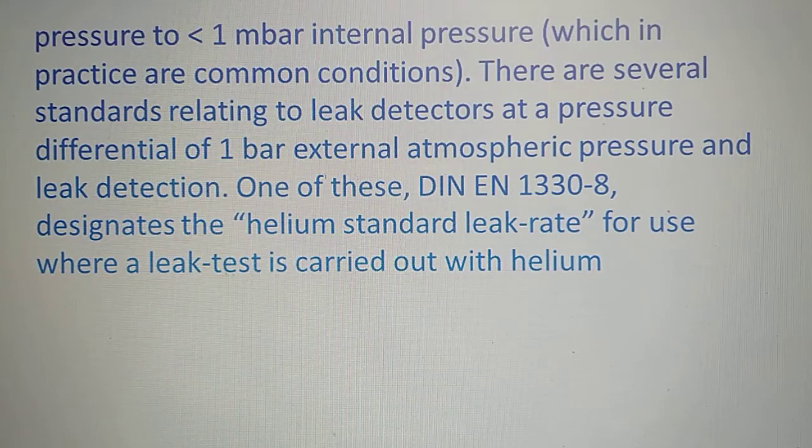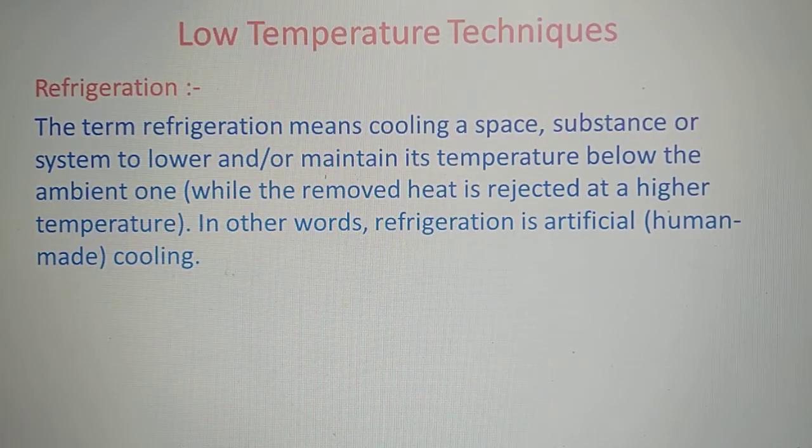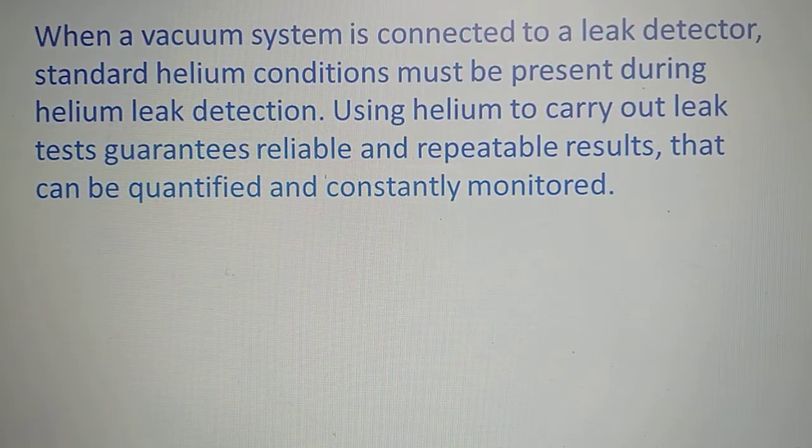One of these, DIN EN 1330-8, designated the helium standard leak rate for use where a leak test is carried out with helium, right? When a vacuum system is connected to a leak detector, standard helium conditions must be present during helium leak detection. Using helium to carry out the leak test guarantees reliable and repeatable results that can be quantified and constantly monitored. So this is about leak detection and leak measurement.